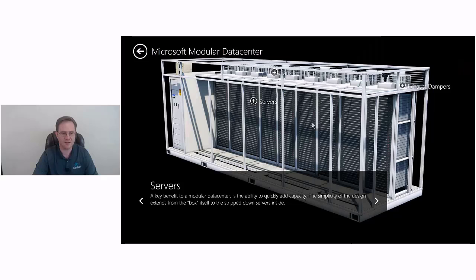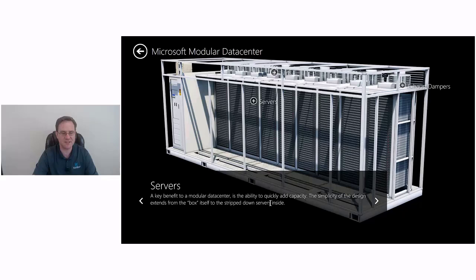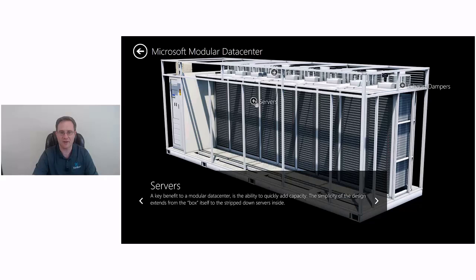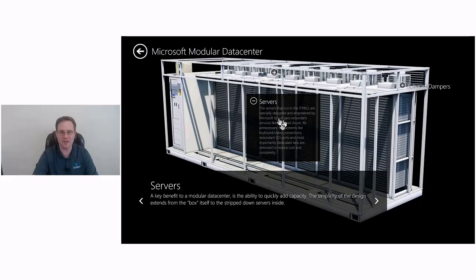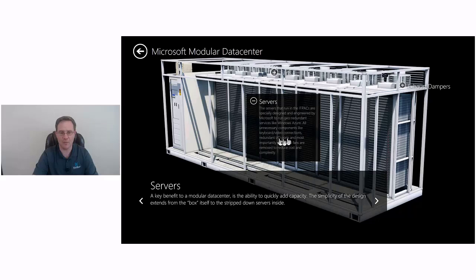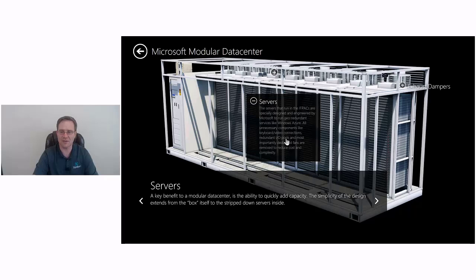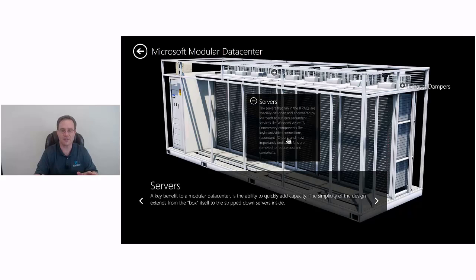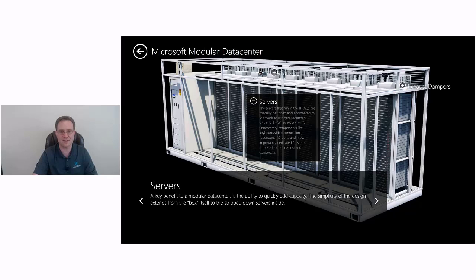A key benefit to a modular data center is the ability to quickly add capacity. The simplicity of the design extends from the box itself to the stripped-down servers inside. The servers that run in the IT packs are specially designed and engineered by Microsoft to run geo-redundant services like Windows Azure. All unnecessary components like keyboard, video connections, redundant I/O ports, and most importantly, dedicated fans are removed to reduce cost and complexity. That's fascinating. Not only did they strip out everything that was not essential to running compute inside these servers, including fans. These servers are sitting here without fans and they're being cooled by the fans and the cooling and the airflow around the unit.